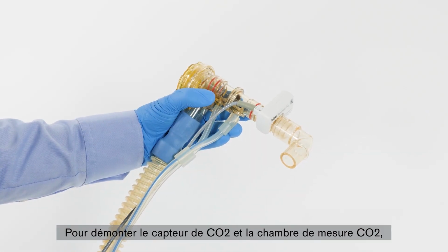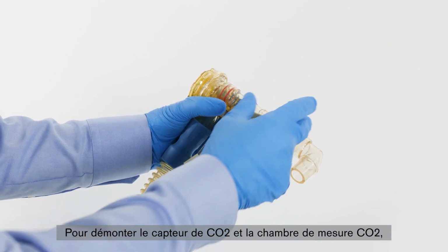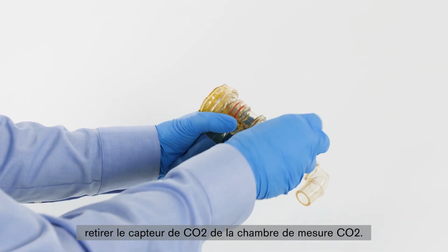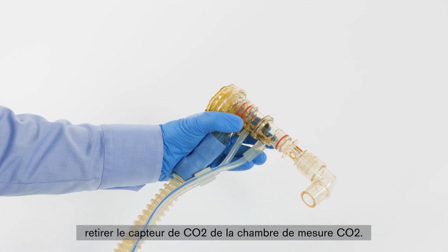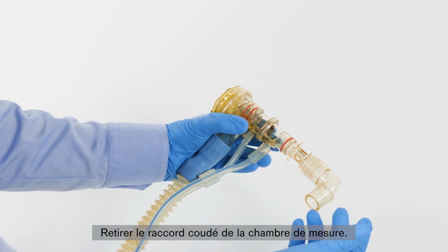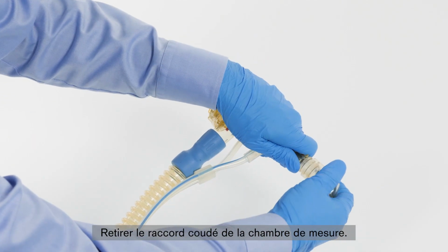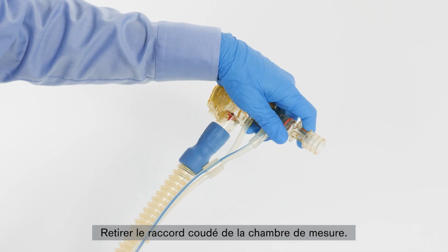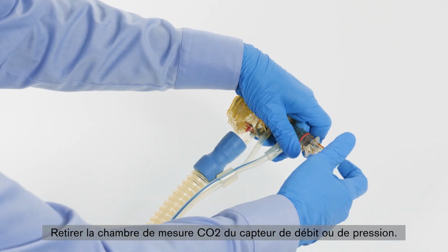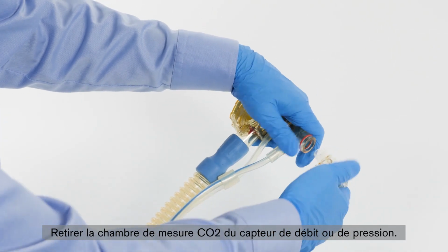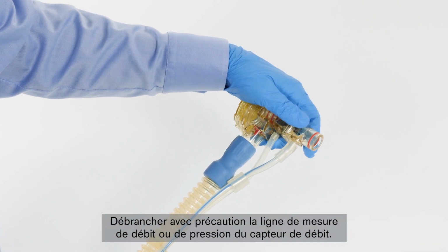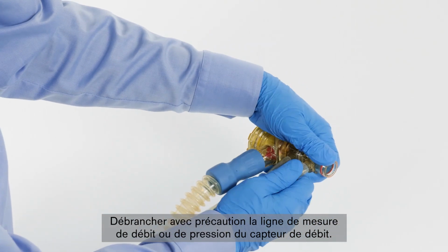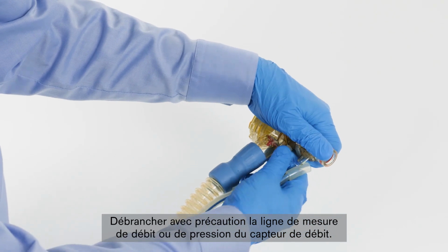To disassemble the CO2 sensor and the CO2 cuvette, remove the CO2 sensor from the CO2 cuvette. Remove the elbow from the cuvette. Remove the CO2 cuvette from the flow or pressure sensor. Carefully and evenly disconnect the flow or the pressure measuring line from the flow sensor.